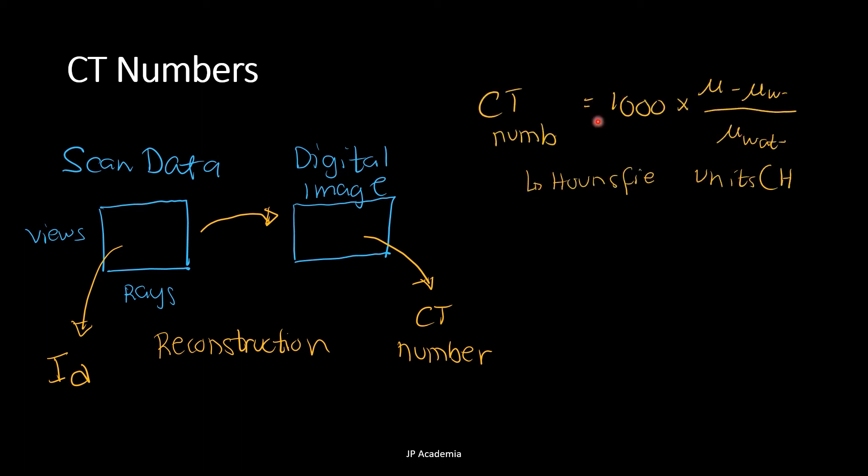The CT number is defined as follows. So this is equal to 1000 times mu, the attenuation coefficient at that specific point of the material, minus the linear attenuation coefficient of water over the linear attenuation coefficient of water. It has a unit of Hounsfield units, or HU.